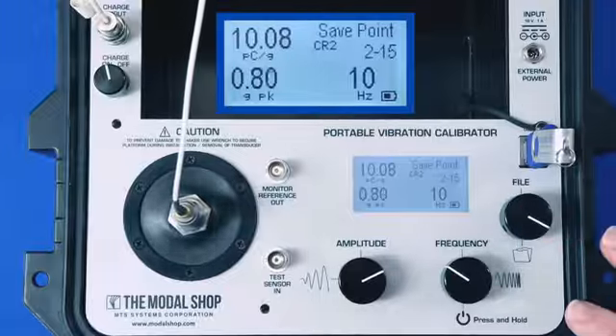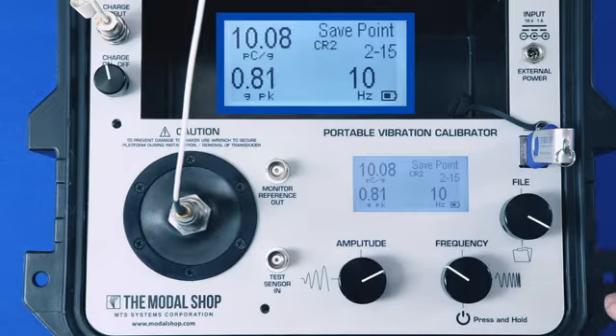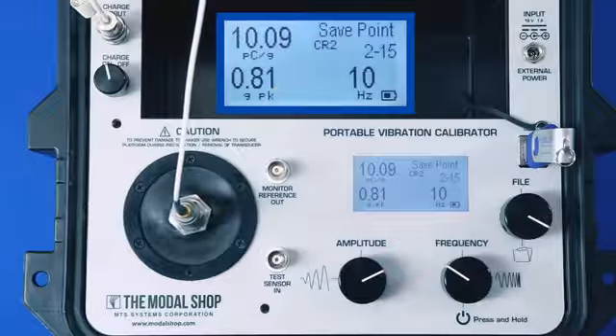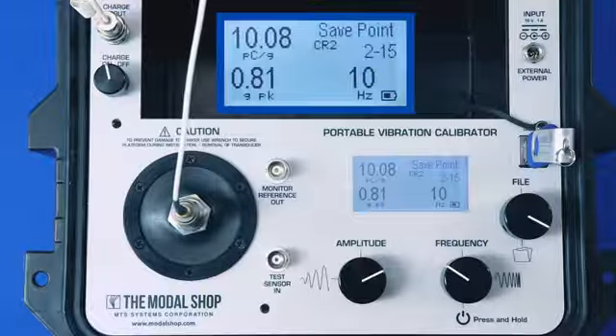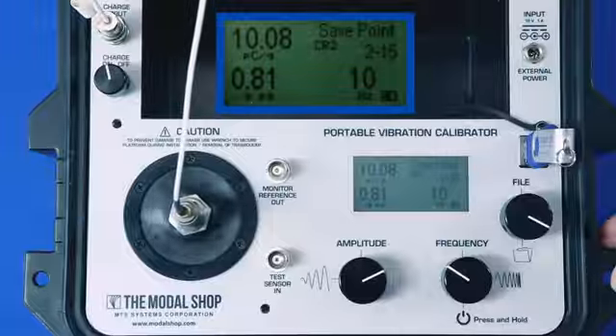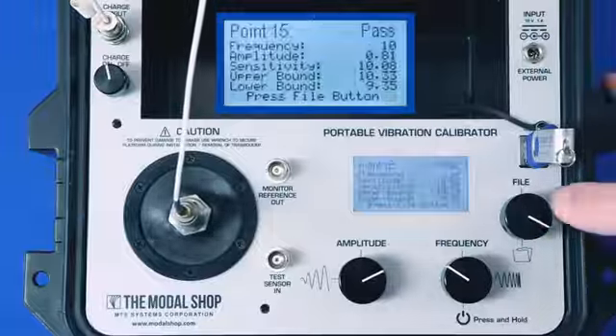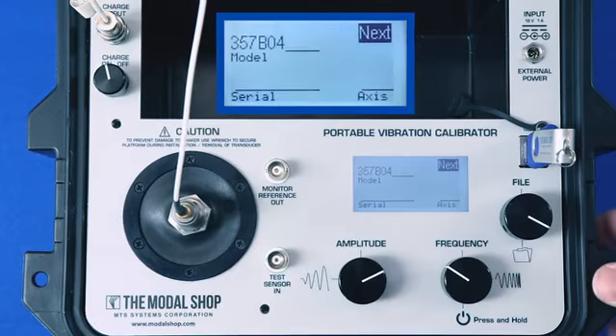I want to point out one thing, that I programmed 1G peak, but at 10 Hertz the shaker is not powerful enough to generate 1G peak. So the calibrator is going to give me the maximum amplitude that it can achieve without causing damage to the mechanical structure of the device, and that's 0.81 G's peak. So it will not allow you to program something that's going to cause damage to the shaker. It'll prevent that and give you the actual vibration amplitude on the screen there and record the data to the memory. So that was a 15-point calibration for the 357B04.